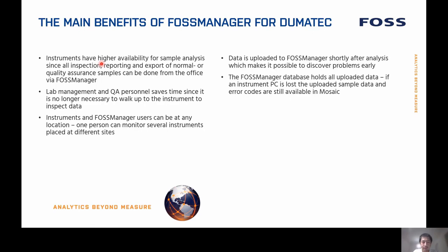And also the instrument and the FOSS Manager user can be at any location, so one person can monitor several instruments at different sites. And the data is uploaded to FOSS Manager shortly after analysis, which means it's possible to discover problems in advance. And last, the FOSS Manager database holds all the uploaded data. If the instrument PC is lost, the uploaded data and the error codes, all this information is still available in the FOSS Manager server, so people can still find the data and the details.